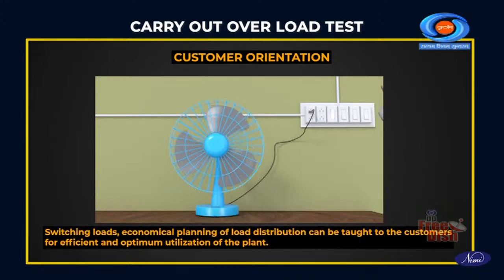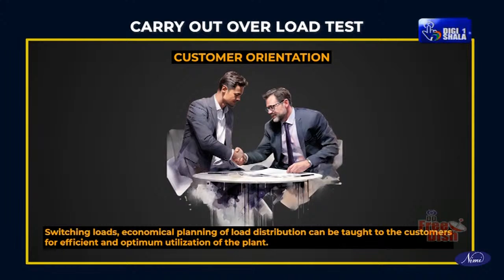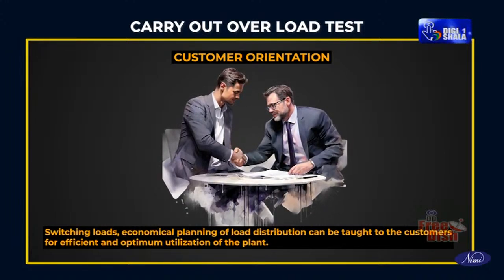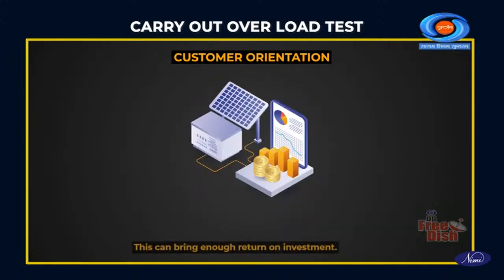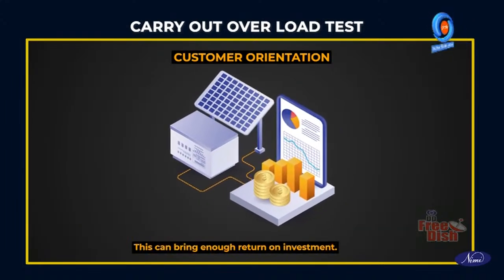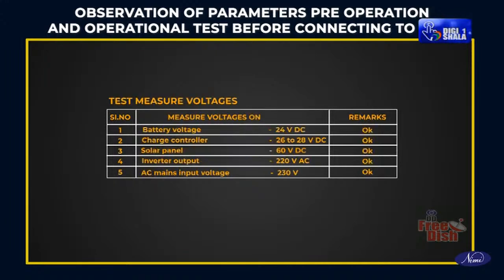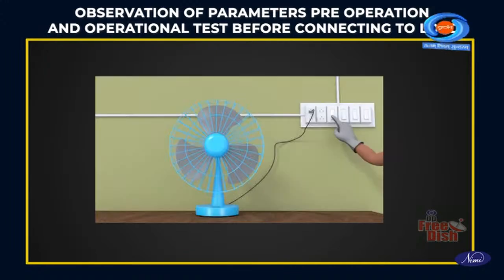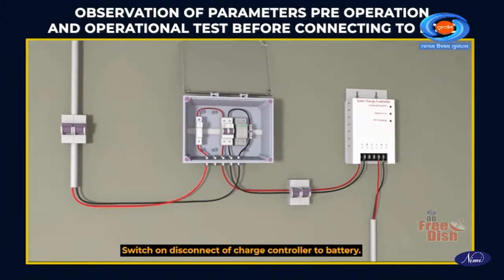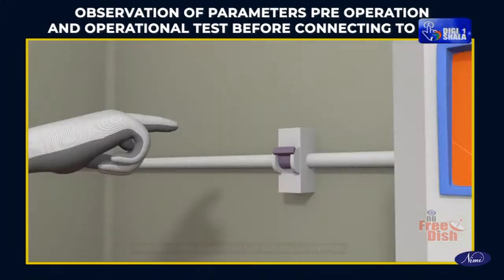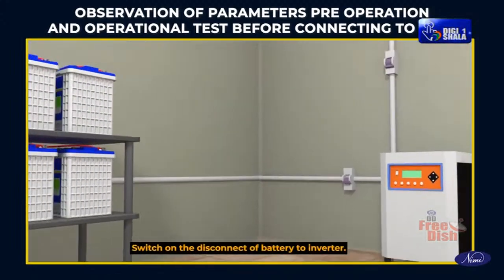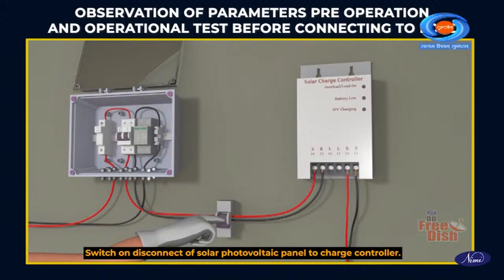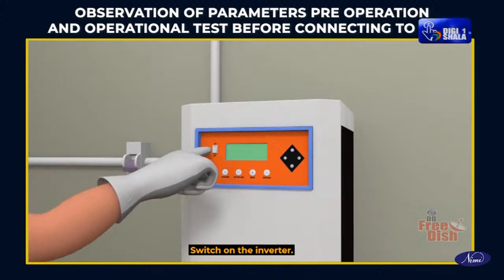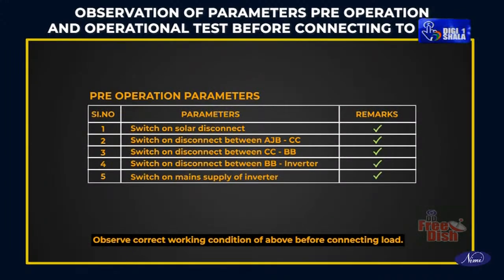Switching loads. Economical planning of load distribution can be taught to the customers for efficient and optimum utilization of the plant. This can bring enough return on investment. Observation of parameters pre-operation and operational test before connecting to load. Switch on disconnect of charge controller to battery. Switch on the disconnect of battery to inverter. Switch on disconnect of solar photovoltaic panel to charge controller. Switch on the inverter. Observe correct working condition of above before connecting load.